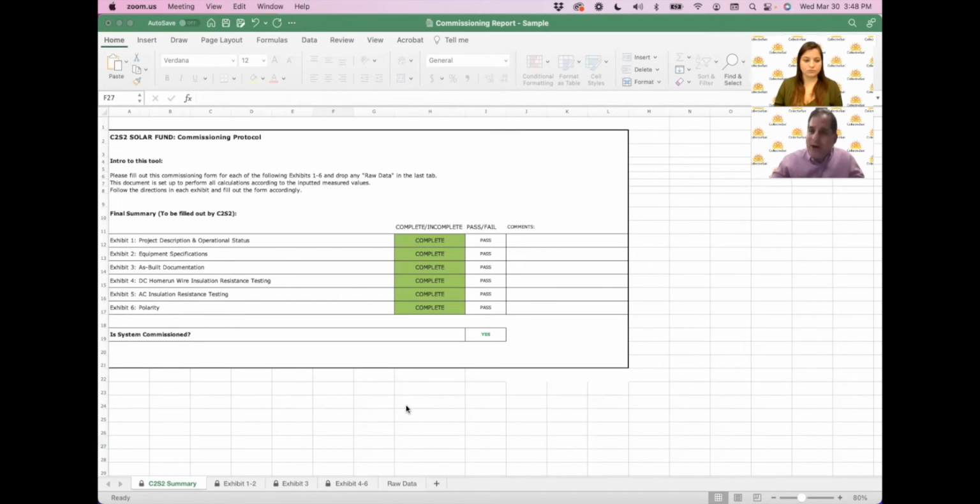Cheyenne, I'll ask you some questions in just a second. The basics of this is that exhibits one or two are a basic project description and equipment. We want to make sure that we have documentation from the contractor of what was installed, and that with exhibit three, it matches the as-built. For those of you, maybe a nonprofit, that aren't familiar with the term as-built, that's literally how the system was built. It may not match exactly the plans that we engineered 6 months ago when the system was first designed, because maybe a supply chain issue meant we didn't get the tier one solar module that we first slated for this. So we used another tier one module, for example, and that would be reflected here.